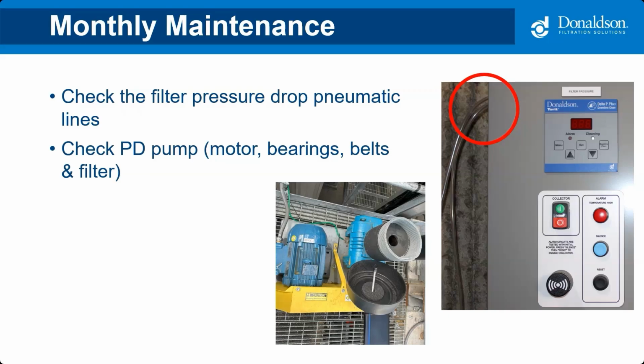And you'll want to blow low 20 psi compressed air backwards through the line, so you're blowing back into the collector, not into the gauge or this digital readout, just to blow out any moisture or dirt that might be in them, and then visually inspecting them for cracks, things like that. Obviously, if they have cracks or they're plugged, you're not going to get a good reading. So now you're losing the ability to actually know if your filters are okay or not.